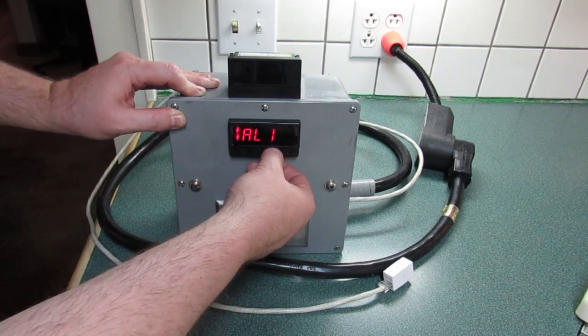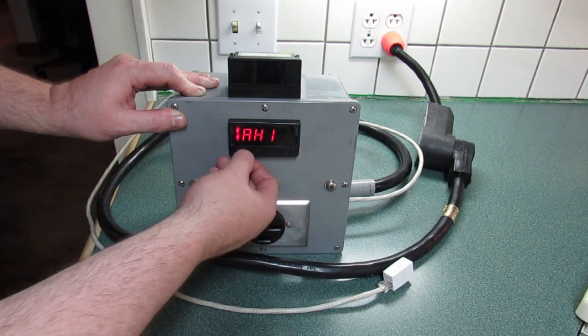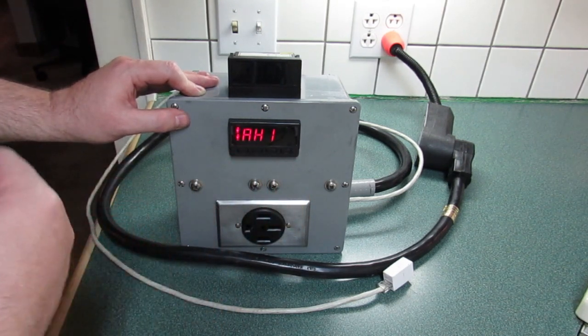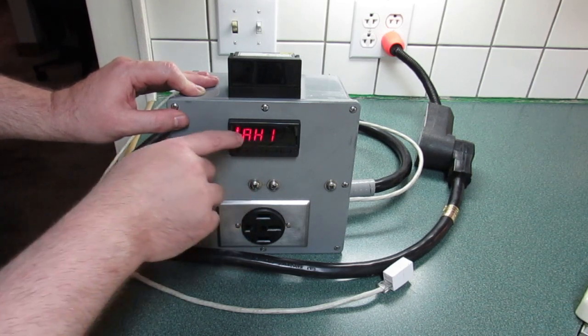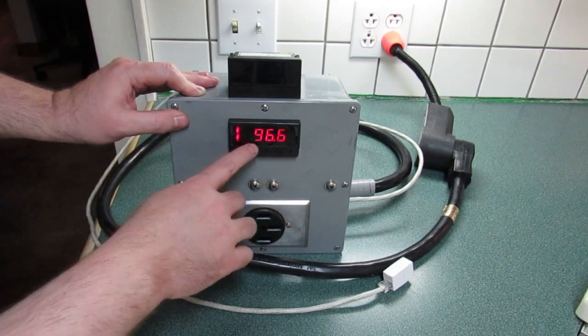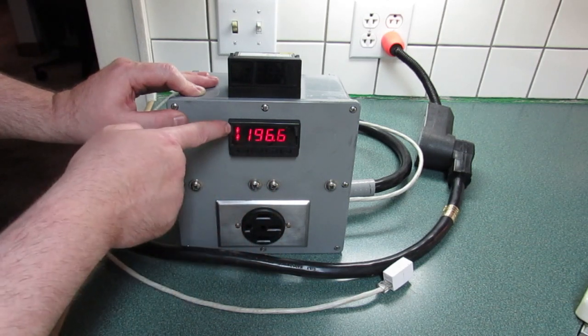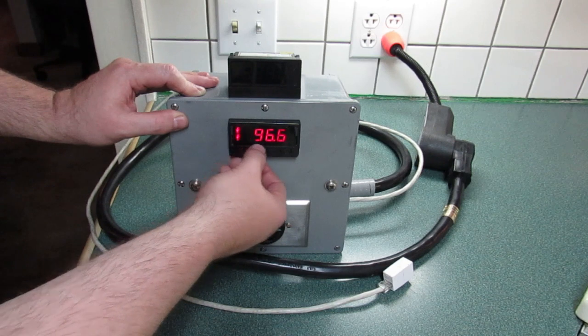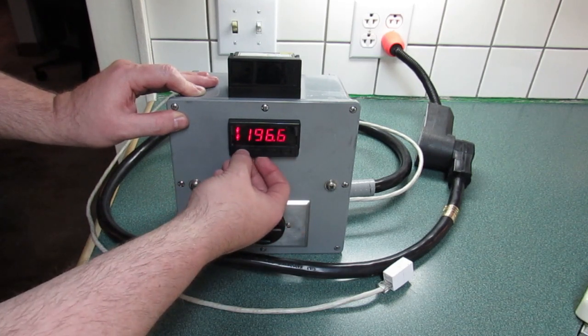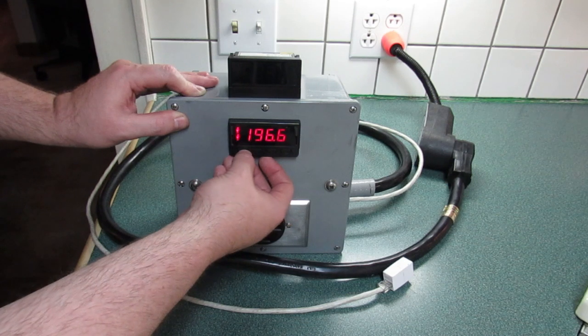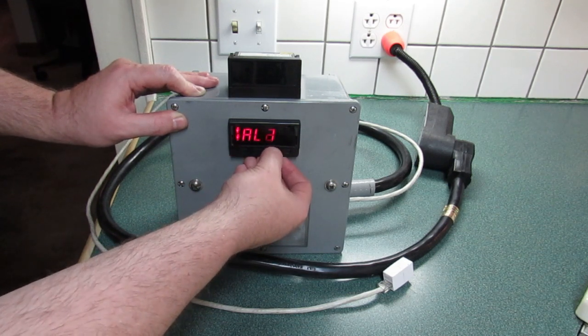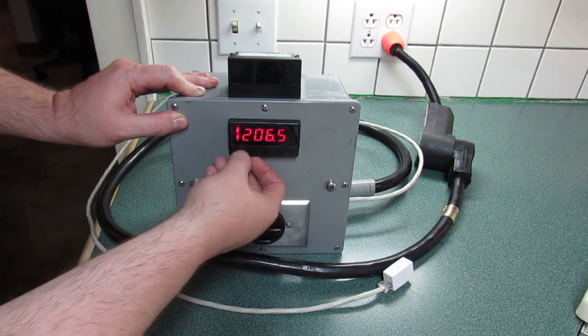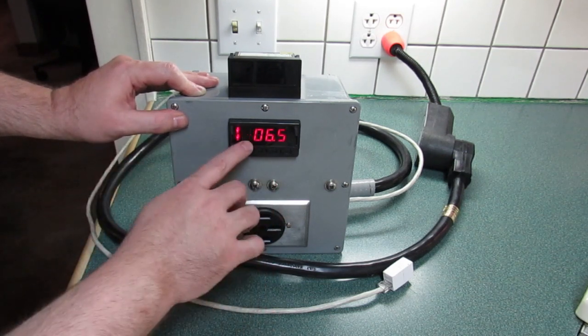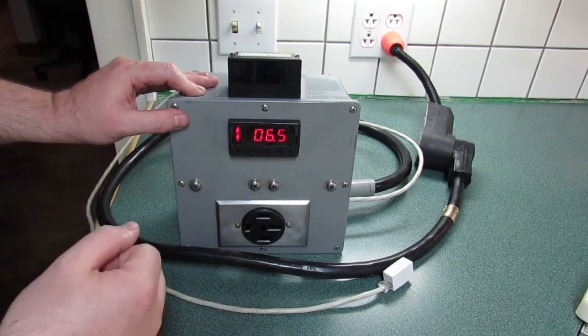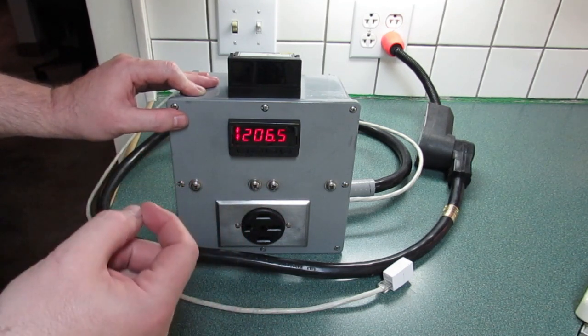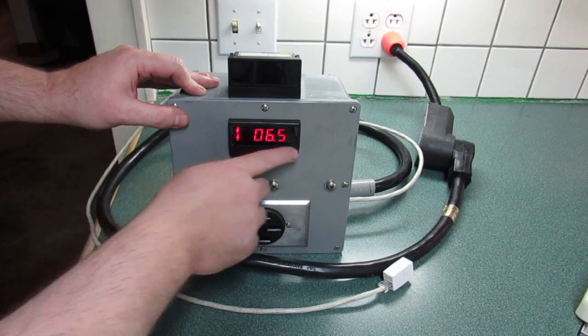And it's kind of odd how you configure these things. I'm not really going to go into it. I've documented it in a previous video. But essentially, your high point is actually where you want your batteries to settle for the first relay. So that's 196.6 for 59 cells of lithium iron phosphate CALB cells. And the L1 is our fully charged point, 106.5. Again, you divide that by 59 and you get your voltage per cell that you are charging up to.